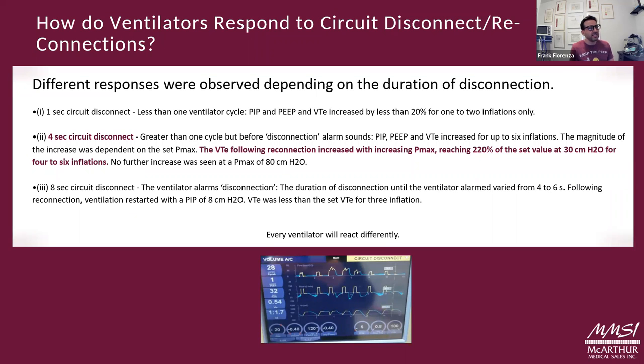But once the circuit is disconnected, it's got to be reconnected, right? So if we look at this study done out of Australia, where they looked at three different durations of circuit disconnect, we're looking specifically at the 4 second disconnect, because that seems to be the most common time frame to change or switch, about a 4 to 10 second window. If you look at this 4 second circuit disconnect, once the ventilator was reconnected, the set parameters reached a max of 220% of the set values.